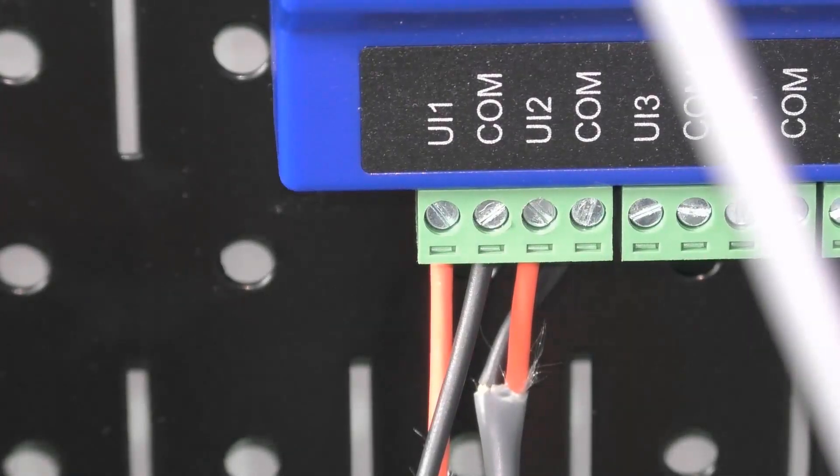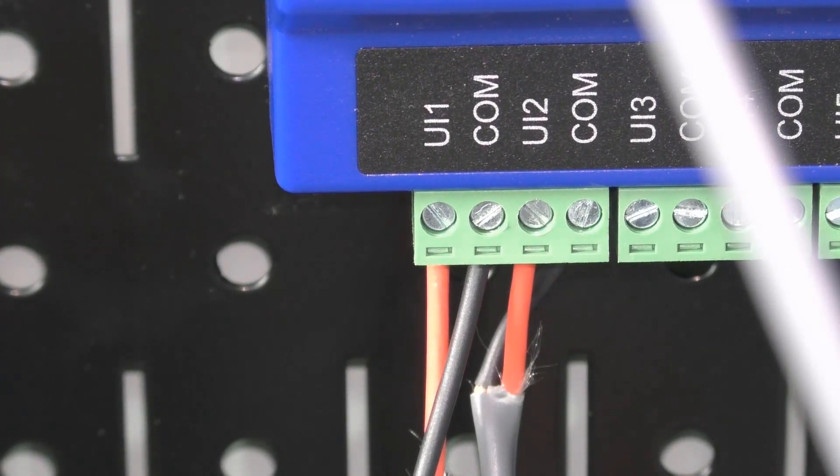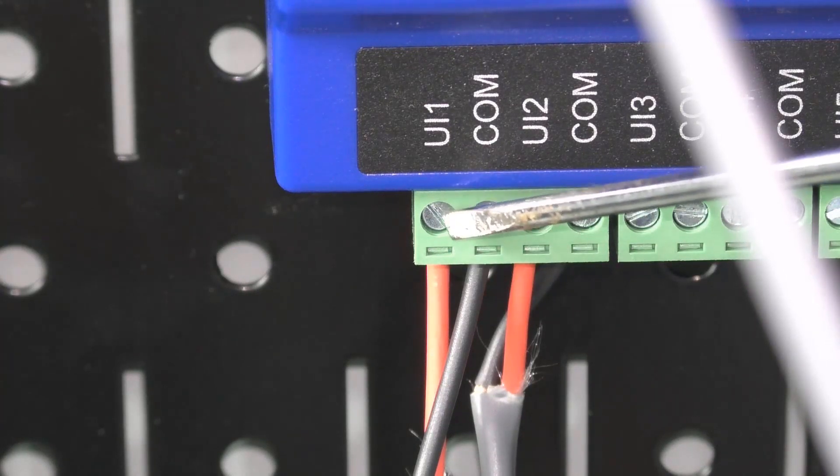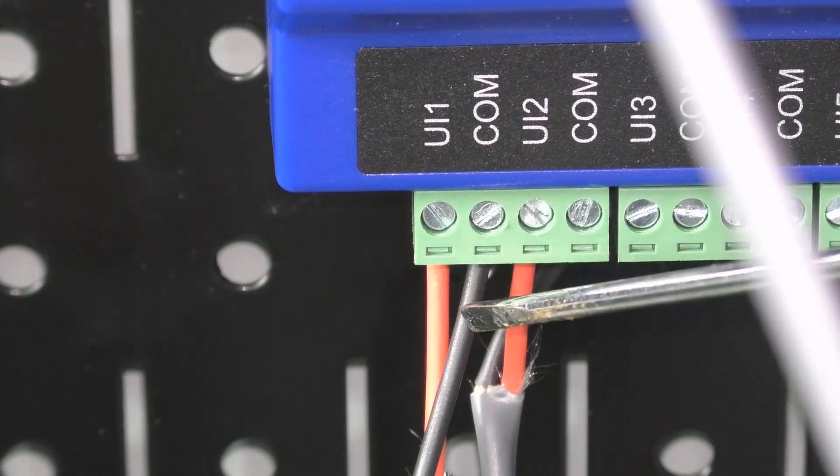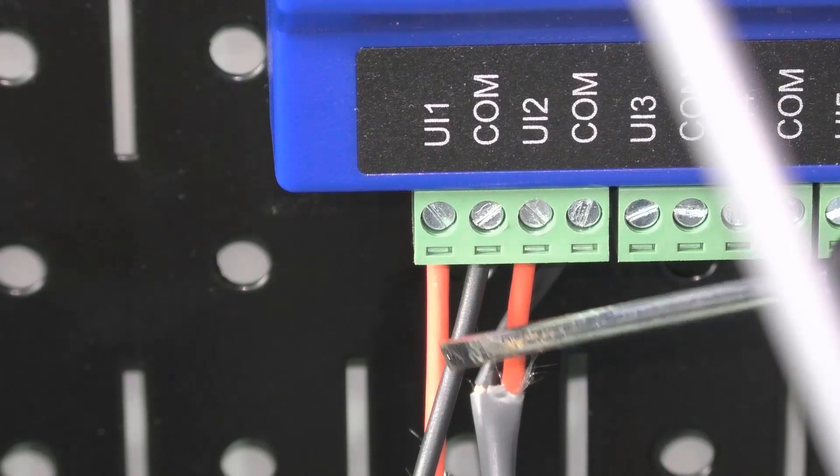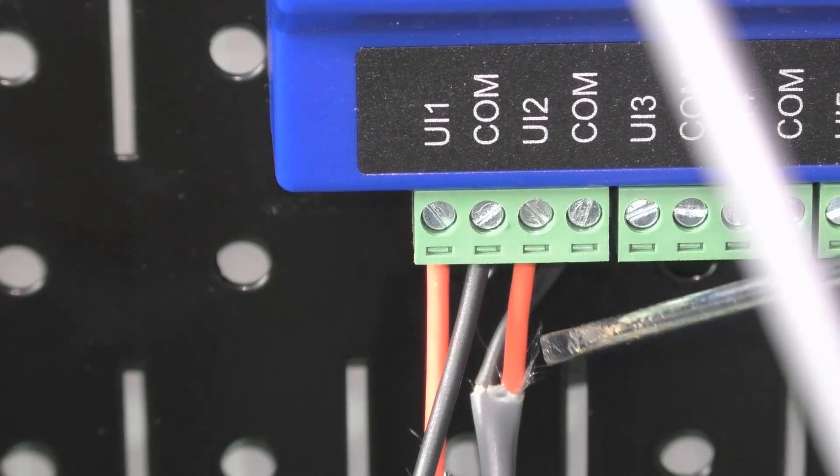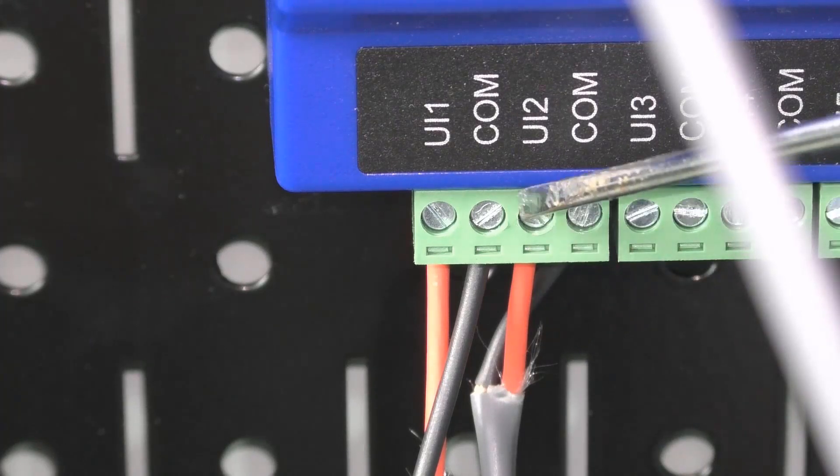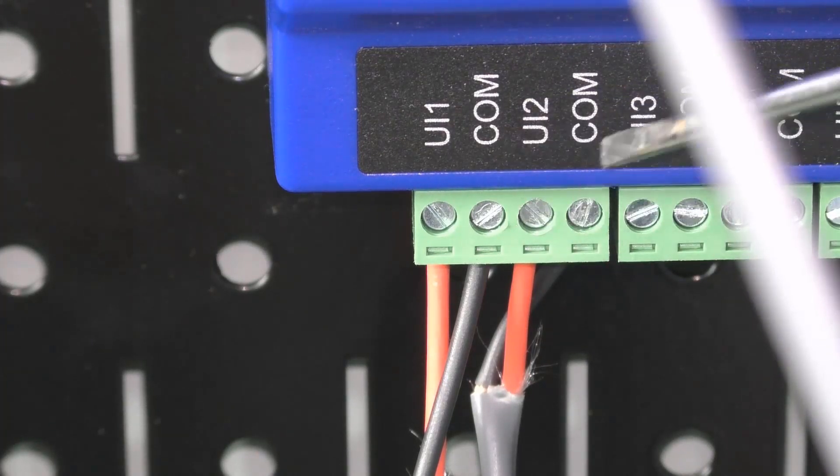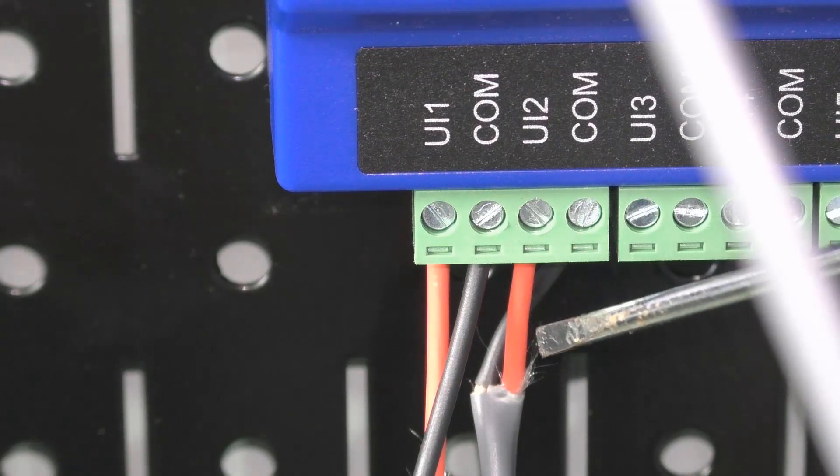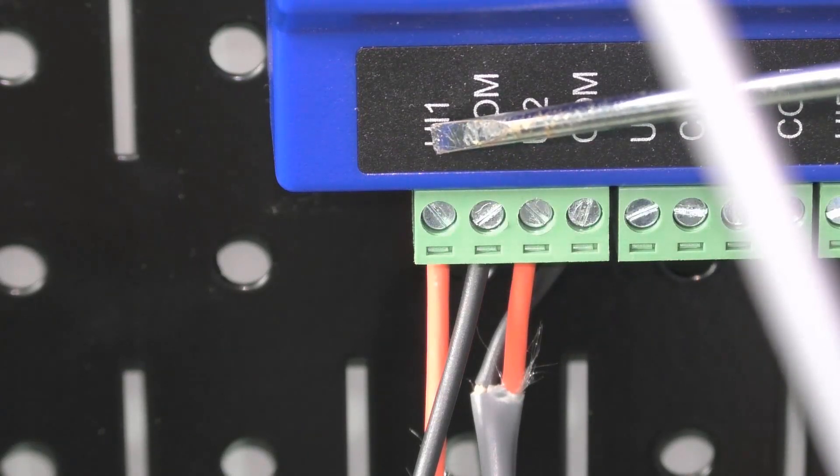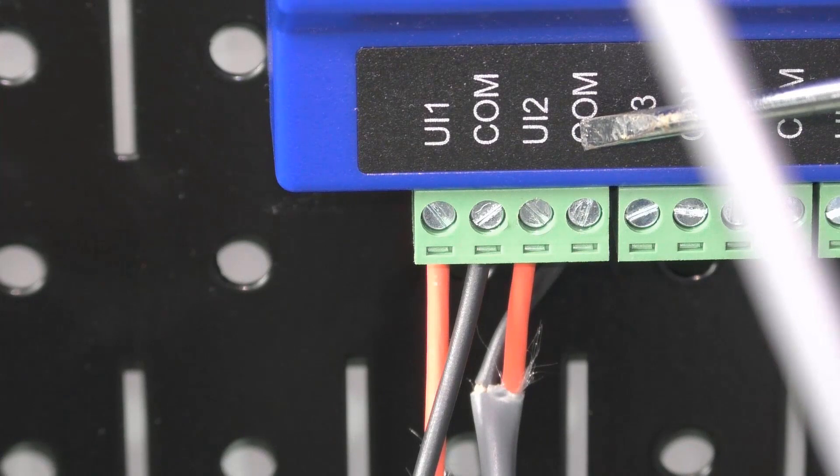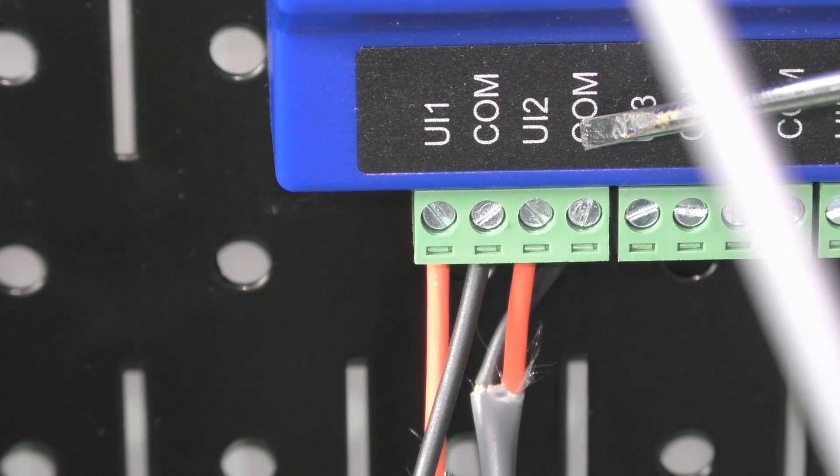Now as we look at UI1 common and UI2 common, we can see that we are using red on the input and black on the common. That's the common standard to use red for our input and black for our common. UI1 is going to be our normally open set of contacts and UI2 is going to be our normally closed set of contacts.